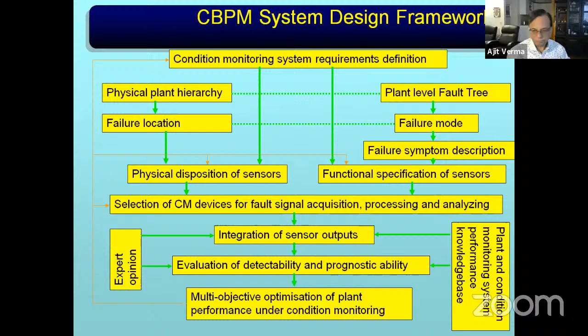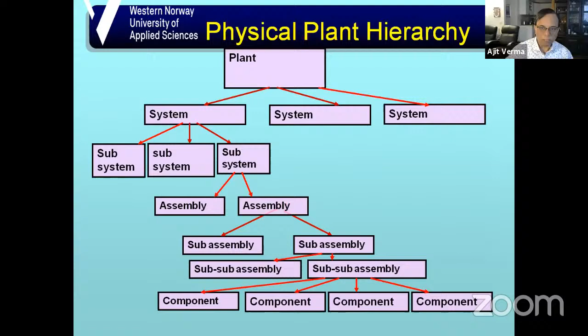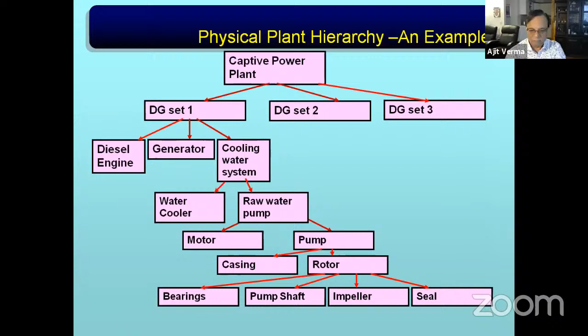Now, a physical plant hierarchy, for example: the plant is constituted of systems, then subsystems and assemblies, sub-assemblies, sub-sub-assemblies, down to the component level. For example, a captive power plant may have 3 different modules, diesel generator sets. Each of them constitutes subsystems like diesel engine, generator, cooling water system. The cooling water system, which is critical, can consist of water cooler and raw water pump, which consists of motor and pump. Then the pump consists of casing and rotor, and the rotor consists of bearings, pump shaft, impeller, seal. So from the system level down to the component level.